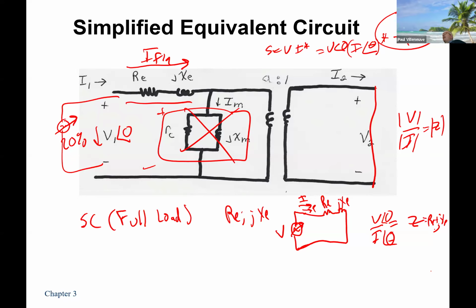Or let me back up. Should I run it on the high voltage side or should I run it on the low voltage side? One's going to have a short circuit. The other one's going to have the power supply and all that stuff. Which one should you put the equipment on to do all your measurements and apply the voltages? The high voltage or the low voltage? Why? Because the losses in the high voltage side would be a lot more.